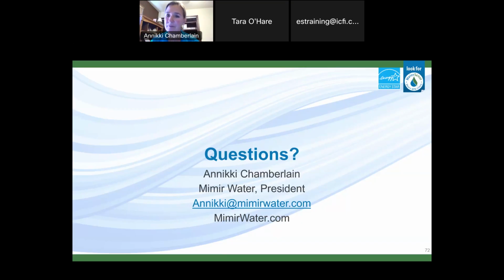Yeah, that it's definitely increased. I'm just going to take one more because we're running out of time, and the rest will be answered via email. If you identify a blowdown problem, is this an issue that would require tower replacement, or could you retrofit the tower to achieve desired results? I don't quite understand what you mean by a blowdown problem, but usually a tower can recover. You might have to do a little acid wash or something on it.